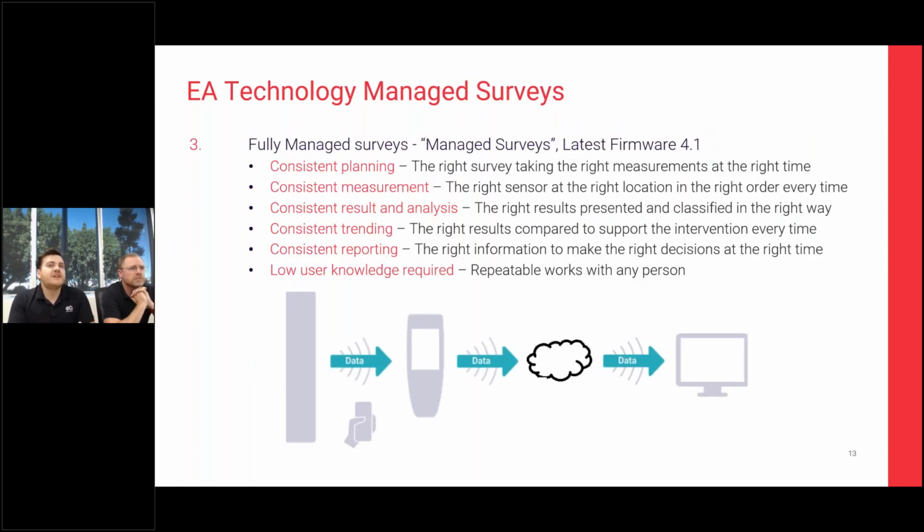So the third option is something that we have been working on in the company, and it is a full end-to-end solution to take that from the inception and the creation of what all the substations you would like tested are, what the tests you need taken are, and then what goes on in the field. So this is something that EA are calling our managed surveys, and it's part of our latest firmware upgrade on the UltraTev Plus 2 device.